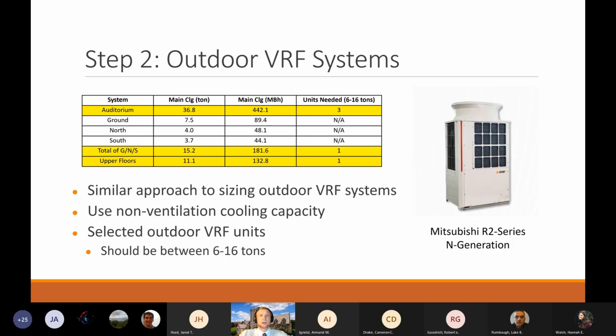So the next step was to size our outdoor VRF units, or the variable refrigerant flow units. These are the units that are placed outside and would supply the refrigerant to the numerous indoor units. So the way that we sized the outdoor units was by looking at the non-ventilation cooling loads on the system checksums report. So this is a different report than the one I just showed you. So the units had to be between 6 and 16 tons each.